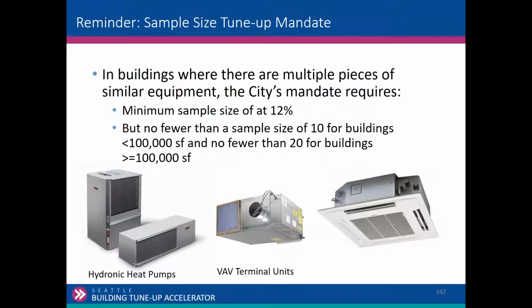So we've mentioned a little bit about sampling earlier when there's multiple pieces of similar equipment. The City's mandate requires a minimum 12%, no fewer than 10, and no fewer than 20 on large buildings. So use sampling. When you're developing your scope of work, fees, costs for doing this work, you're going to want to use sampling. A question has come up: what if I do a sample and I discover that 50% have a deficiency? Is there any requirement that I now have to do another sample? No.